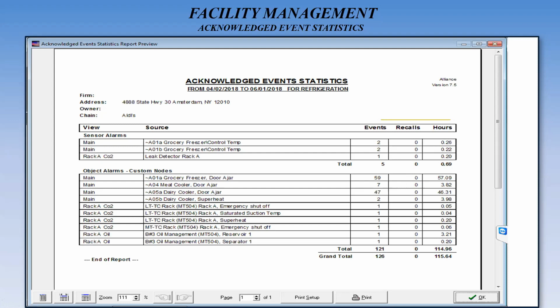Now, if you have a recall on that initial alarm of 30 minutes, that means if it has not come back to proper temperature within the 30-minute recall period, bang, we're going to send out another alarm. We're going to get a red light on that, and we're going to send out an email or a text message. That is called a recall.